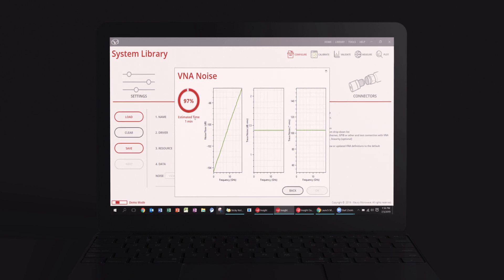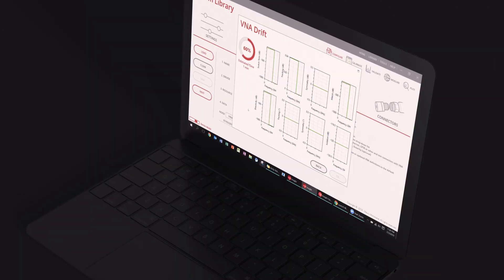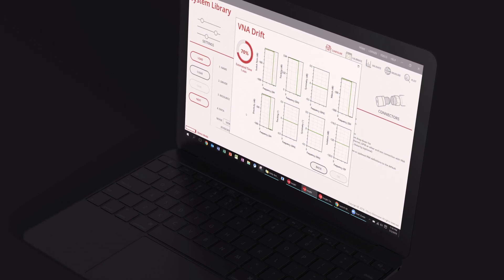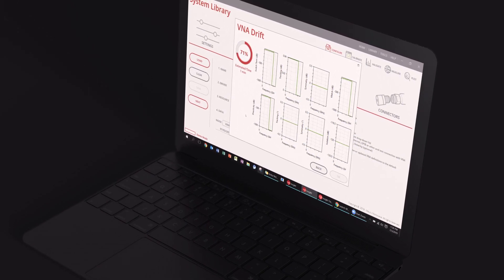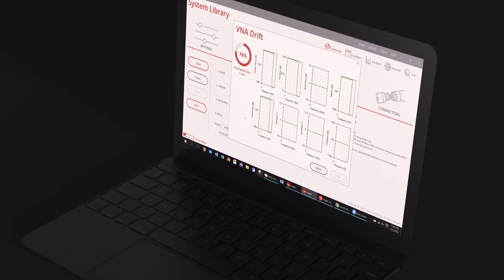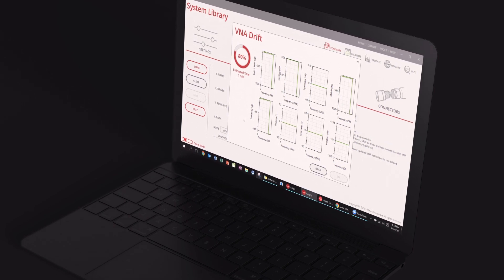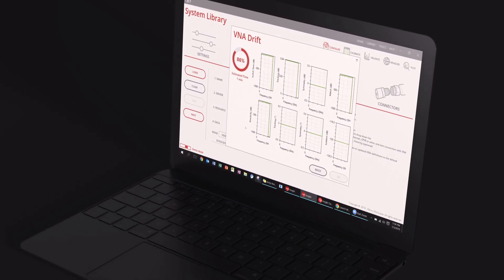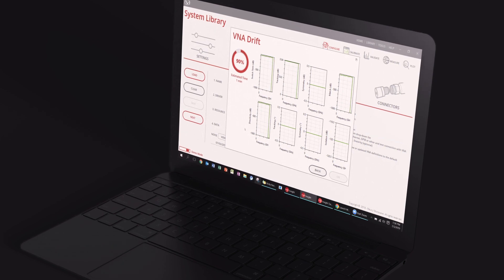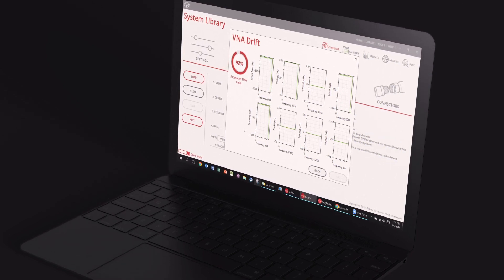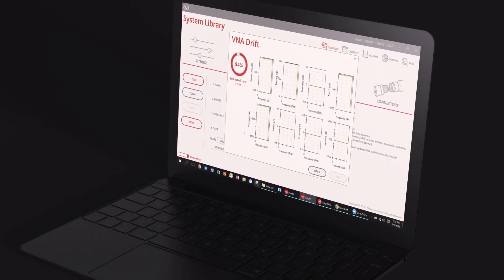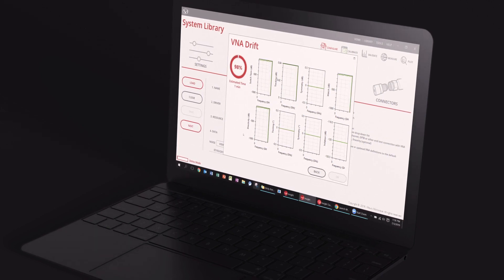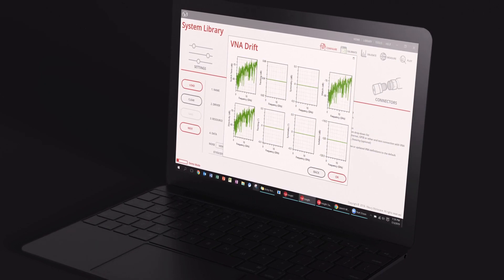Users can also characterize the uncertainties of VNA drift over time, including switch terms, tracking magnitude and phase symmetry, magnitude and phase match, directivity, and isolation. These uncertainties are measured and quantified for the specific VNA in use and do not rely on any generalized or specific data provided by the VNA manufacturer.